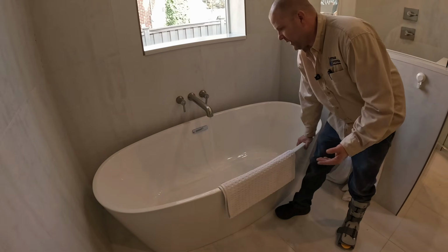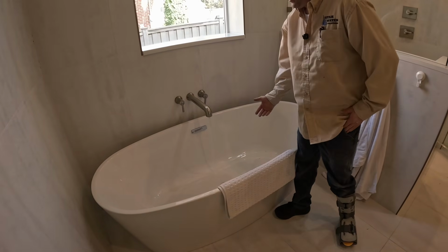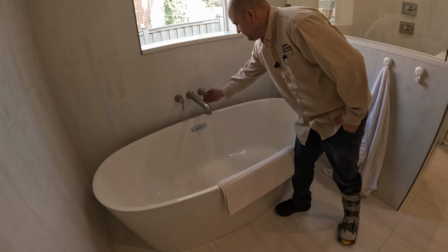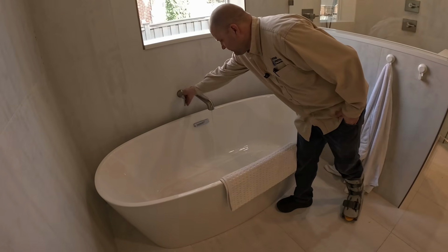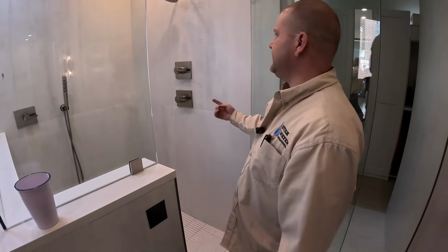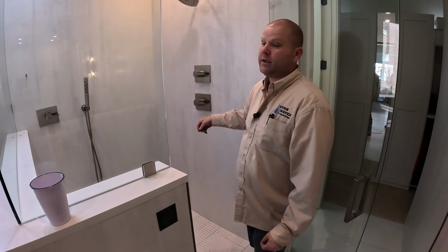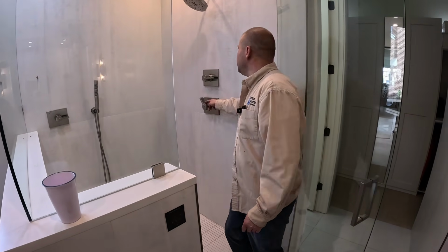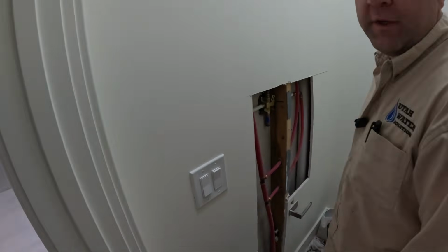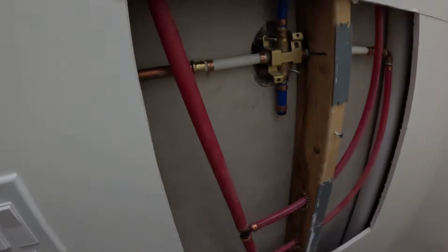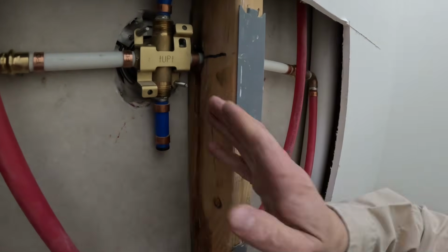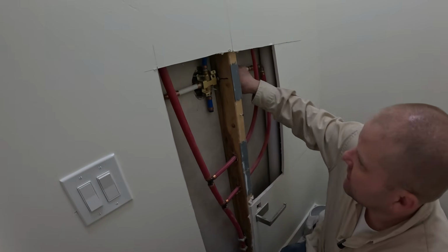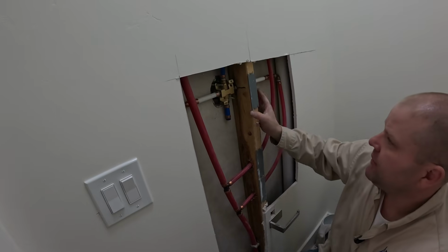So you get a little bit of air. Usually just let it run for a few seconds. It's running clear. Go ahead and turn it off. Run this, that way we get any air out of here to get a proper test on our connections. Make sure that there's actually water there. Most important thing, get comfortable. So here we are, just checking these connections. Got the water on, we've tested, verified, everything's holding good.